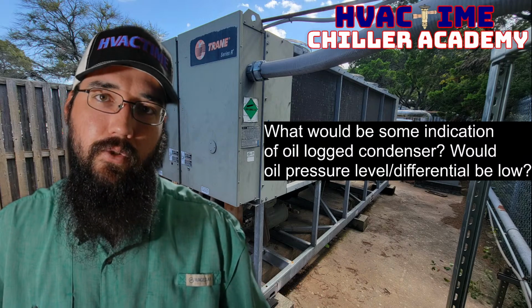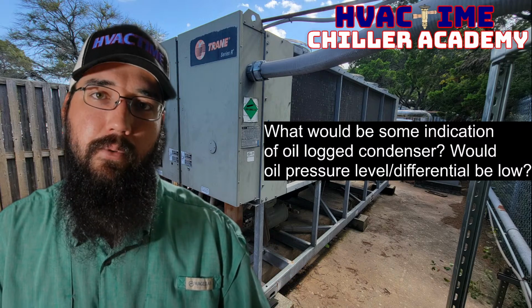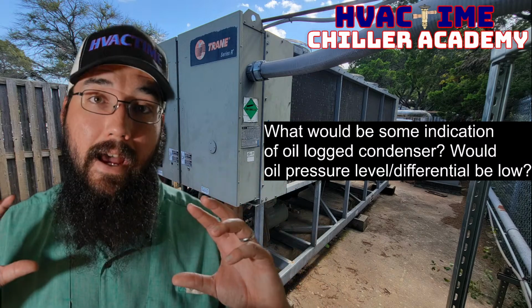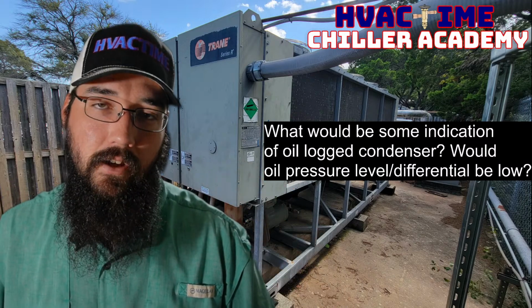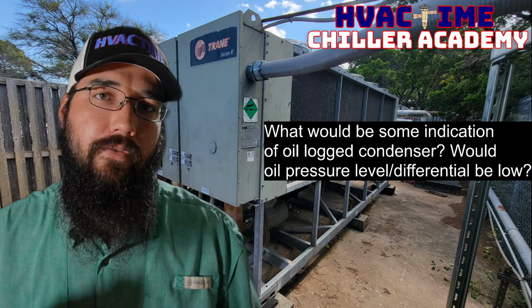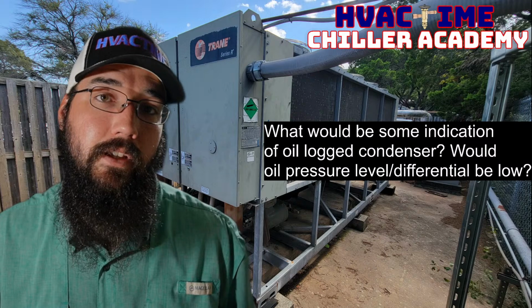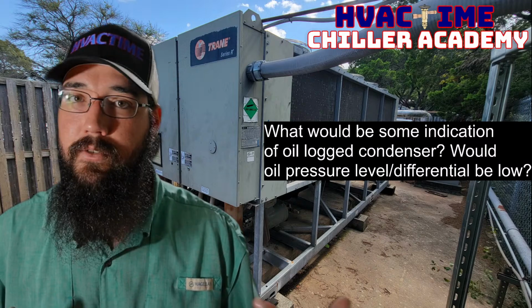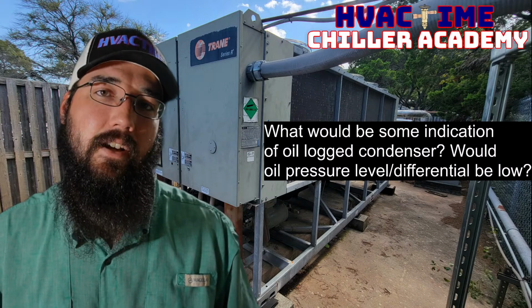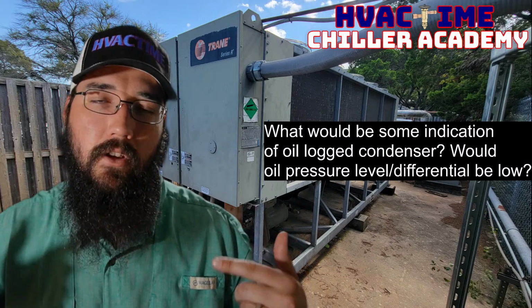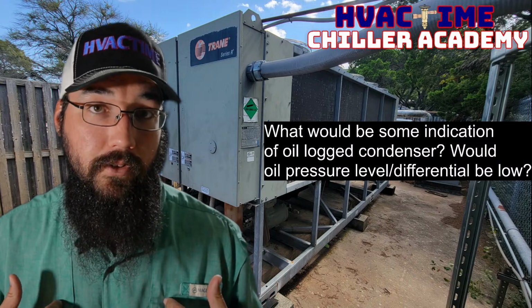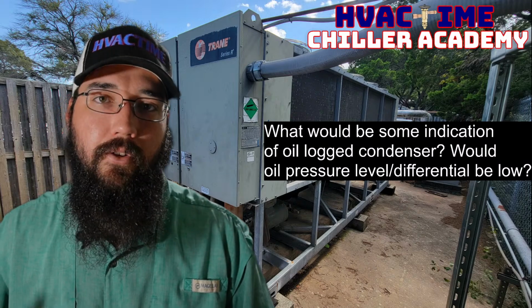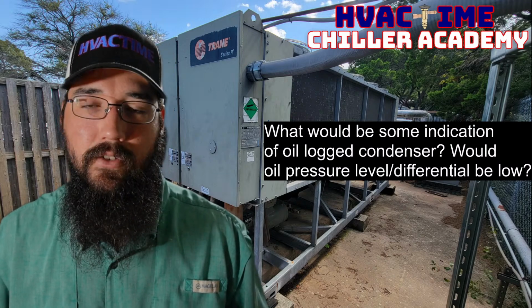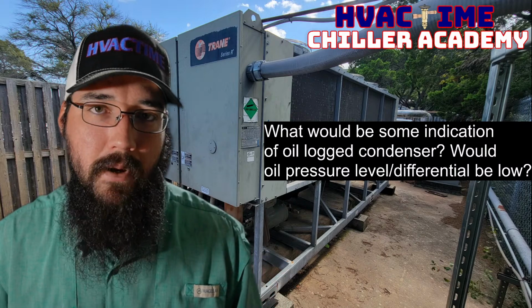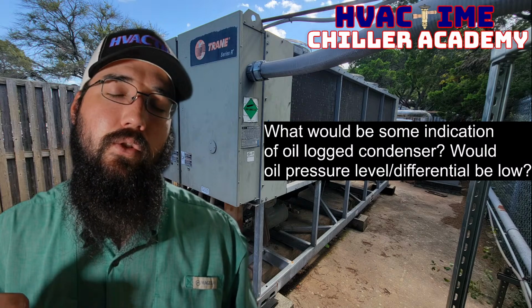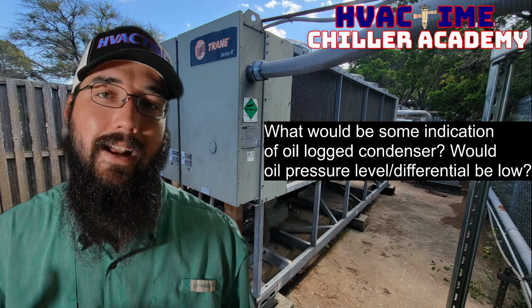What that allows us to do is, whatever oil makes it to the evaporator, it has the ability to get carried back in a way that it can't with the other style, which is why with DX or braze plate evaporators you don't see oil recovery systems. You don't see eductors. You don't see gas pumps. You don't see those things with that style of evaporator, because as long as we can maintain velocity, we can maintain oil return. But that is not true with the other styles, hence a recovery system is needed. So the evaporator is going to be the place that you primarily collect oil. Heavy oil leads to excessive, call it high, approach values.